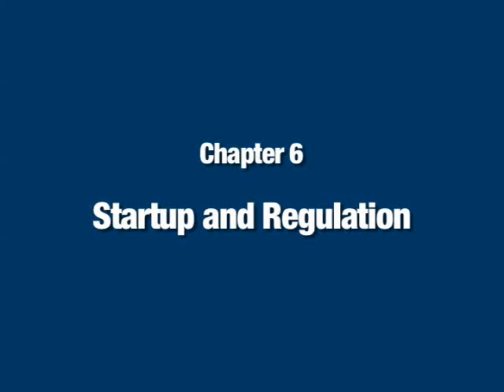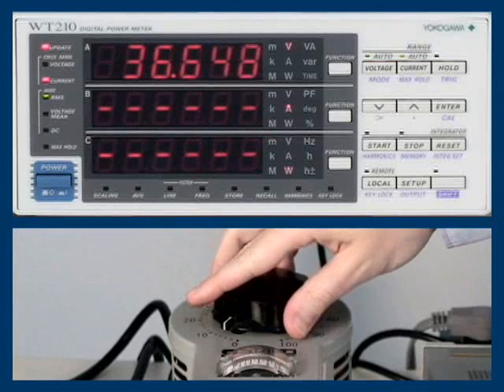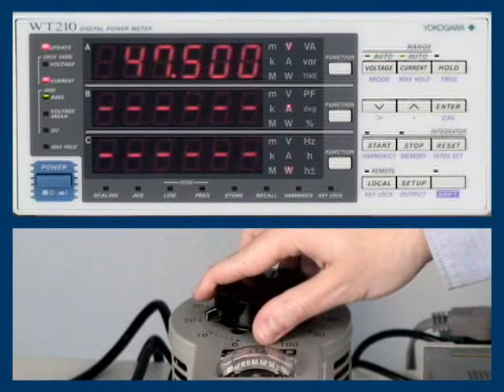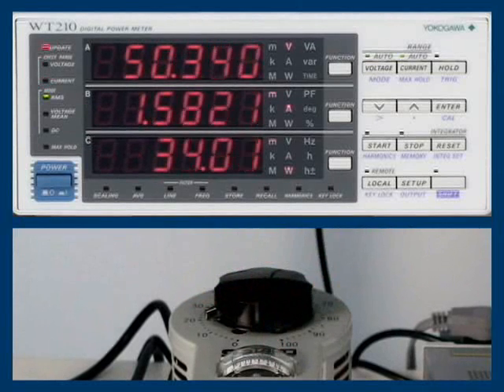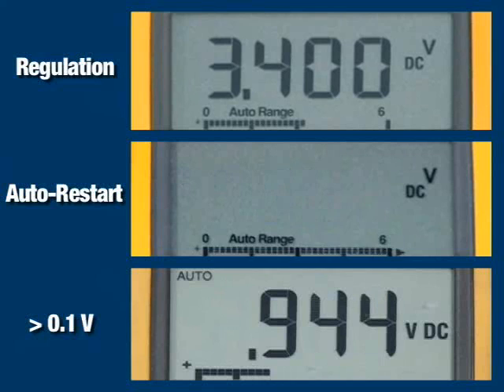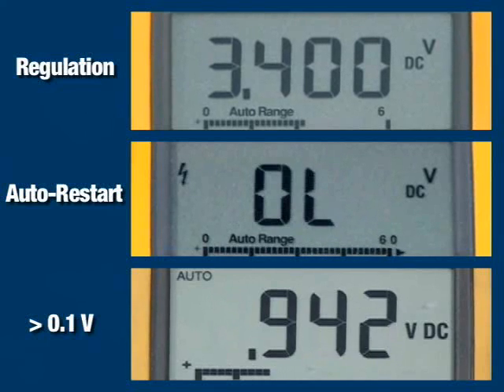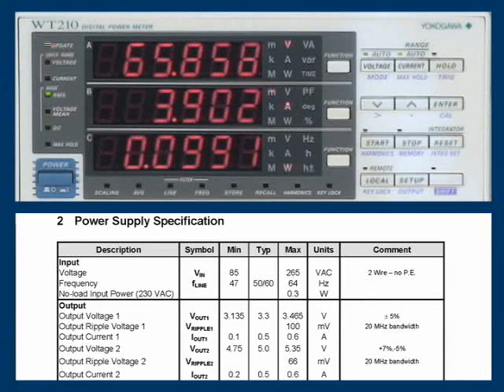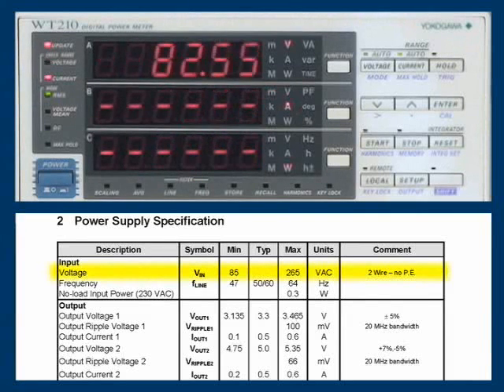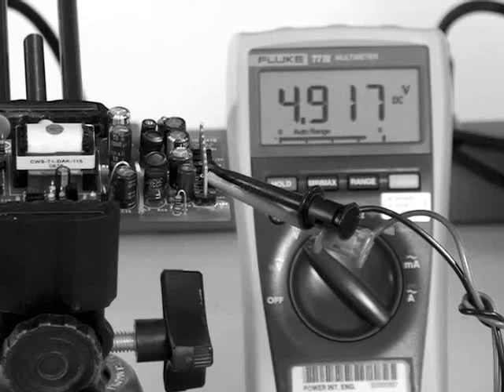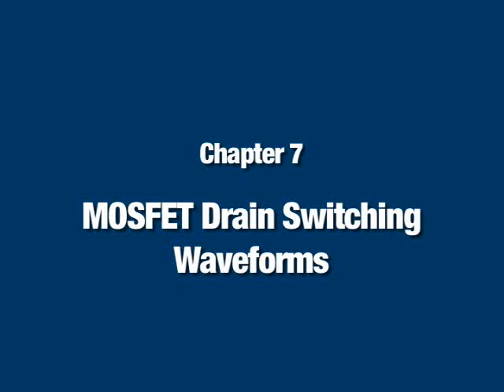Chapter 6: Startup and Regulation. If the input power is less than 15 milliwatts, then continue to increase the voltage to 50 volts AC. Looking at the DC output voltage, if the output is in regulation, is in auto restart, or the voltage on the output meter is greater than 0.1 volts, then the chip is not damaged and is functioning normally. Continue increasing the AC input voltage to the specified minimum input voltage. If the power supply doesn't start up or reach regulation, stop testing and refer to the PI University troubleshooting curriculum to fix the problem.